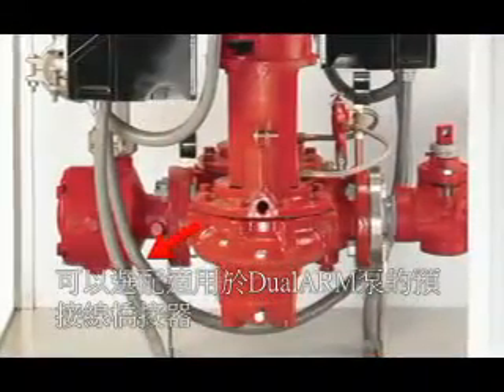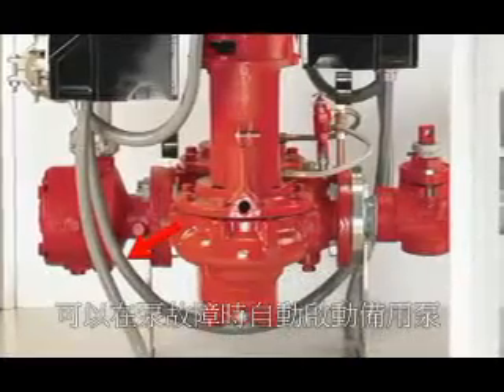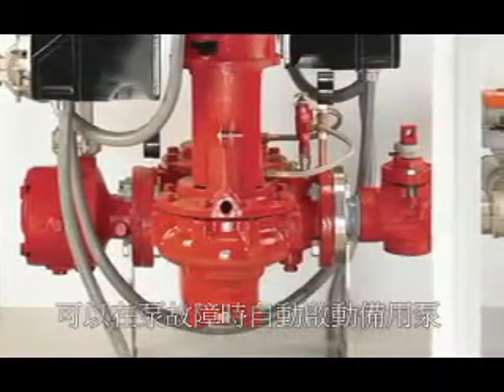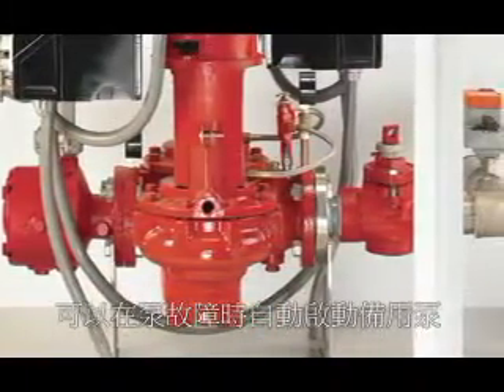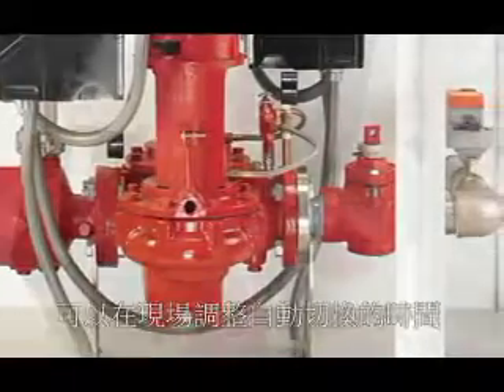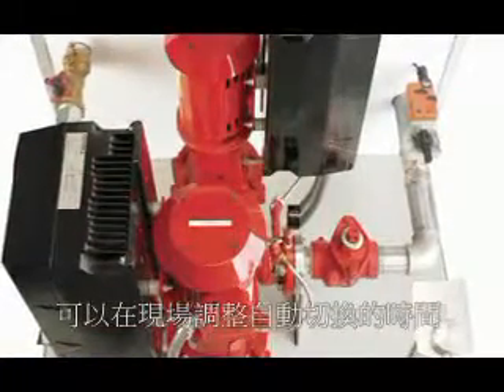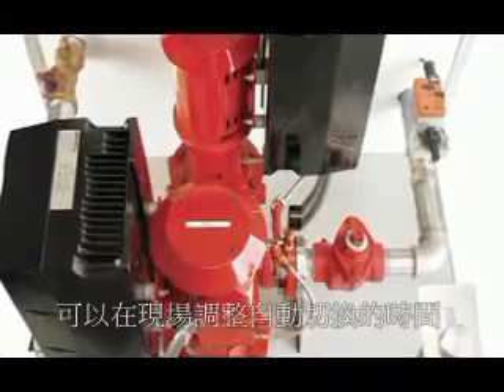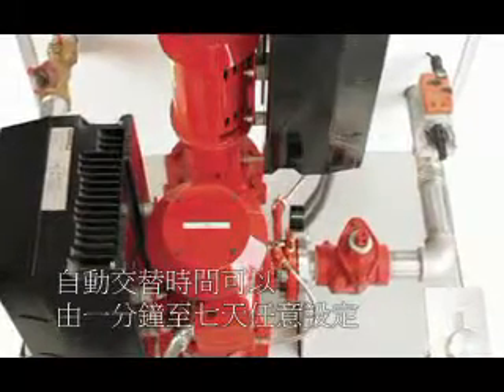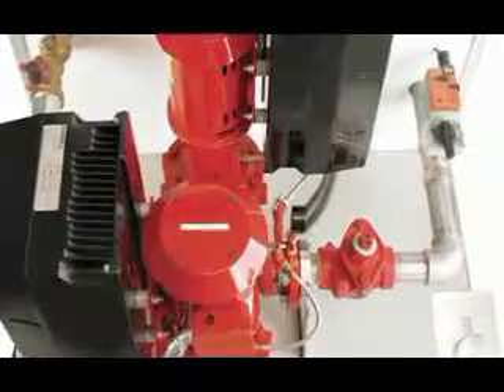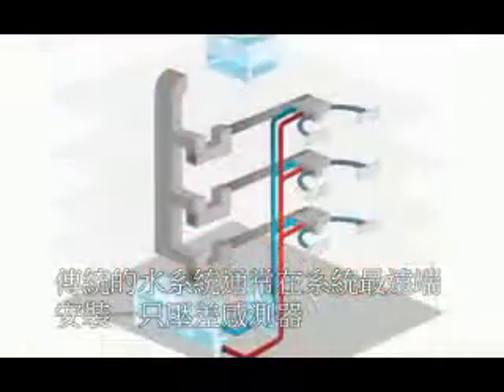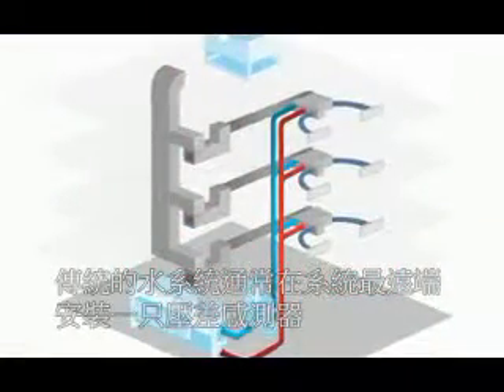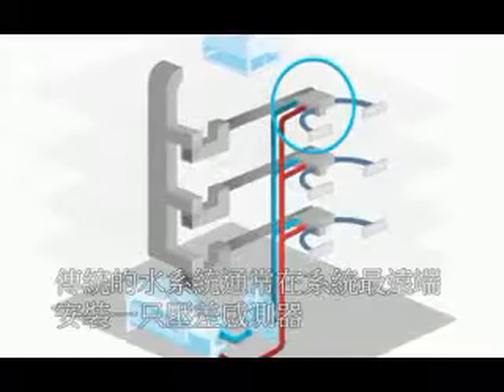An optional pre-wired bridge for our dual-arm or twin pumps allows the standby pump to start on fault or to alternate for equal pump wear. Automatic alternation can be adjusted to a desired time setting on site, anywhere between 1 minute to 7 days of alternation time. A traditional installation typically includes a differential pressure sensor located at the furthest point in the system.